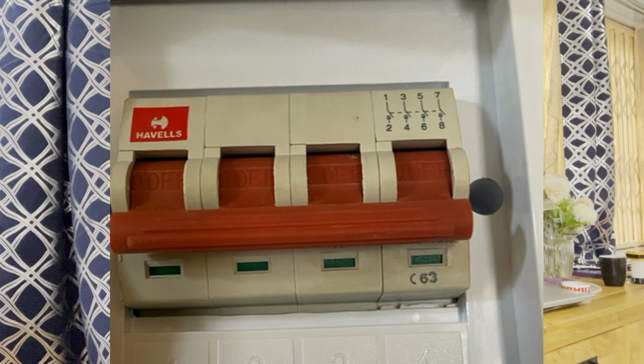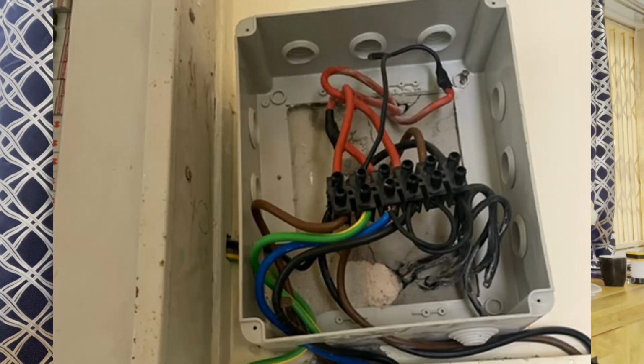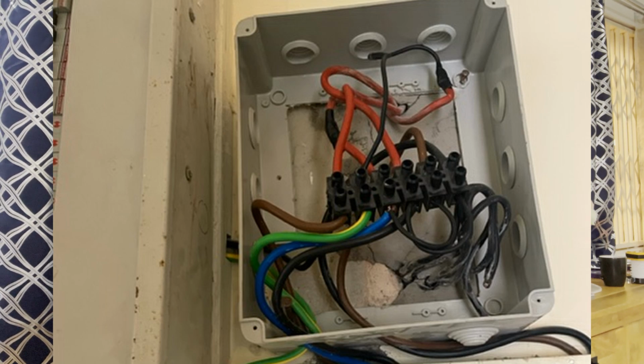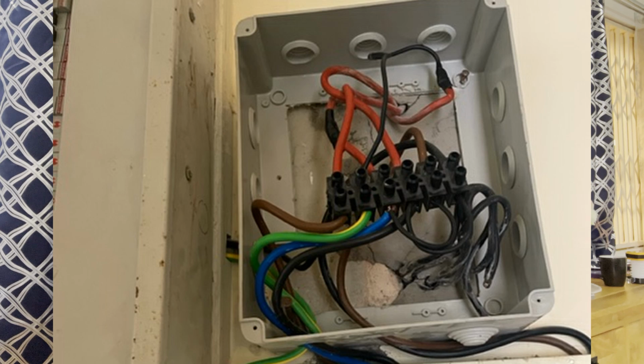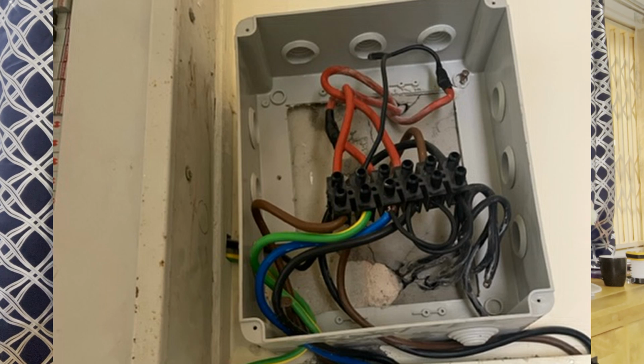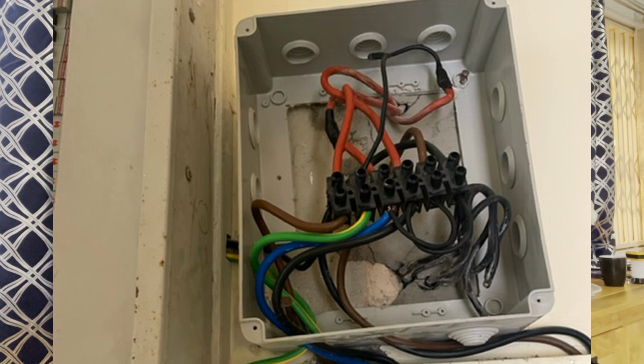Okay. Also, there's a junction box coming on your screen. This is very dangerous. He had a number of cables. There's some cables coming in from the changeover, fairly sizable cables, I think 16mm cables, and he's joined them into this sort of connector, but he's looped them with a smaller cable. Whoa, why? Why would you join a smaller cable to a larger cable when you are supposed to be conducting the same amount of current? That is wrong. The cables in that junction box should all be the same size. Error. Massive error. Dangerous as well, because that could cause a fire.